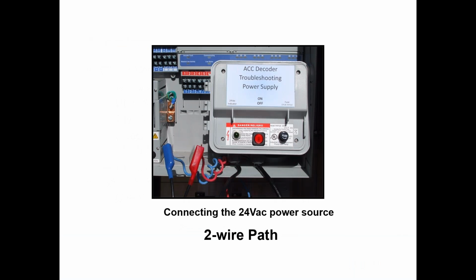All right, we're going to take a look. This is a typical 2-wire supply. This one's progressed a little bit more. There's a 110 to 220 or 110 to 24 volt transformer inside, and it's got an on-off switch. Coming out where the 24 volt side is, you can see there is a red and blue that hook into your 2-wire path, and you can see it's not hooked into your controller. You do not want it hooked in there. At that point, you can go ahead and turn it on, and it will send 24 volts down the line.